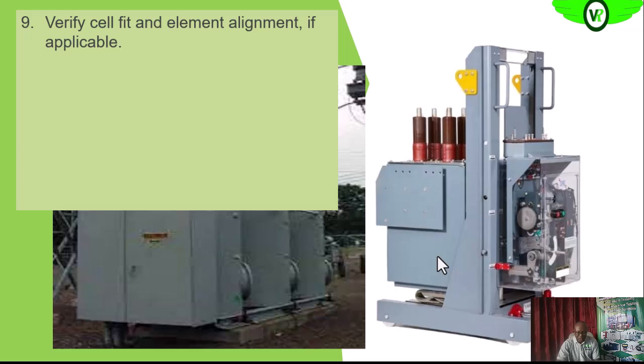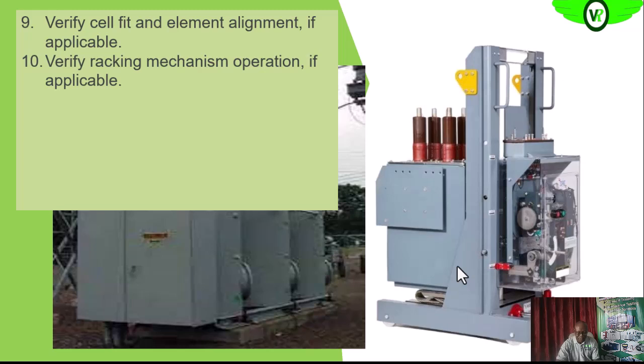Then we also want to verify, especially for those that are racked into the switchgear cabinet, that it is properly fit into the cell, with proper alignment between the circuit breaker and the cell, if that is applicable in our case. Then we want to look at the racking mechanism to see if it is operating properly.